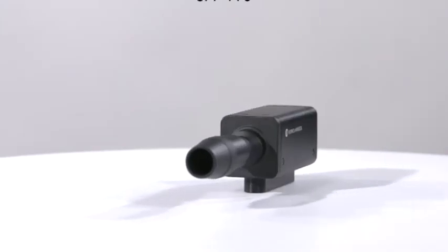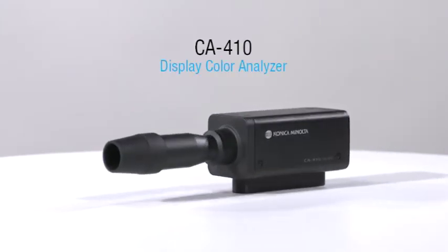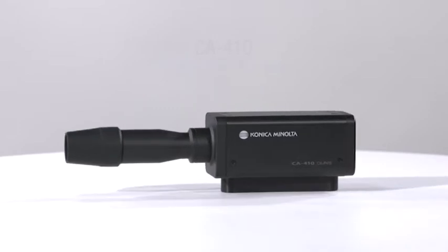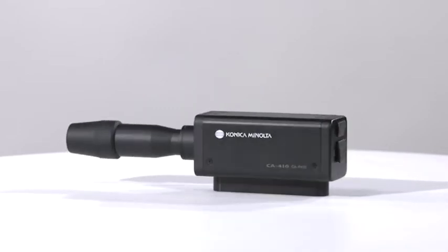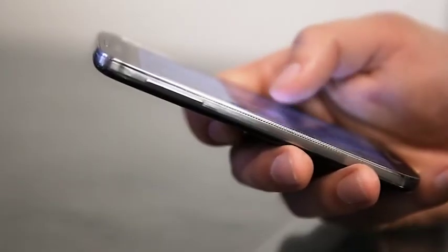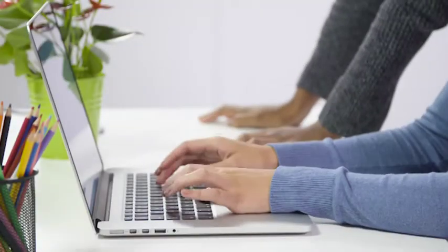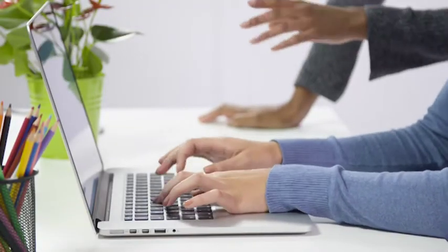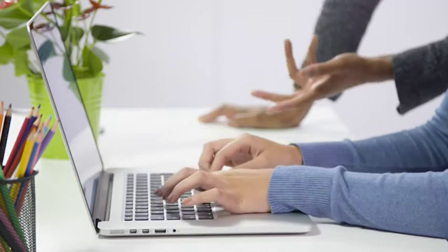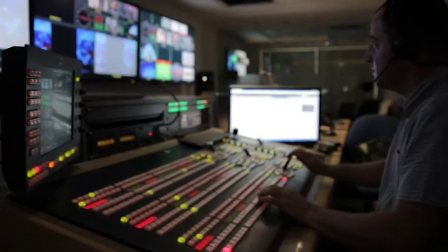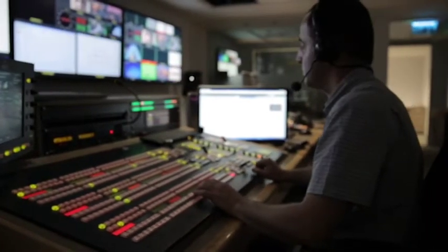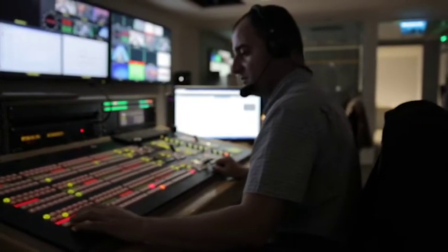Konica Minolta's all-new CA-410 is a breakthrough in display color analysis, designed specifically for the evaluation of increasingly sophisticated modern displays, such as high-end OLED screens, including backlit LED displays, LCD TVs, and smartphones. With more and more displays becoming HDR, the pressure is mounting for color analyzers to improve their measurement performance at both high and low brightness. By using new sensors and circuitry, the CA-410 realizes an accuracy guaranteed brightness range 25 times wider than its predecessor.